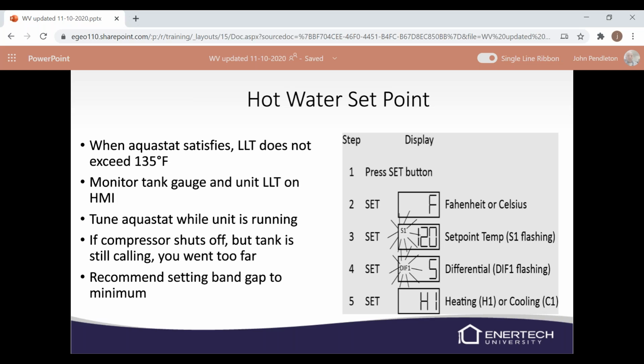A lot of times they set the tank temperature, I see out in the field, around 120, 125 degrees. Obviously, if we can go lower than that, we will, but that's normally where we set it. Basically, we're going to monitor the tank gauge until the leaving load on the HMI does not exceed that 135 degrees, and we can tune that aquastat while it's running. So if the compressor shuts off, but the tank is still calling, you've gone too far and the unit's reached its max temperature, basically. So we'll have to dial that set point down a little bit.